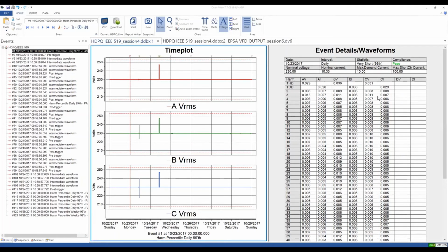The statistical engine of the instrument looks at the nominal voltage, and it looks up in a table in accordance with the standard and says, these are the compliance limits. And then of course it compares the limits to the measurements made by the instrument, and gives you a pass or a fail. You can see these are all pass. These are all the real time measurements done at that time, or the statistical measurements done by the instrument, for both voltage and current on each of the 3 voltage and 3 current channels. And it'll give you the pass-fail results.